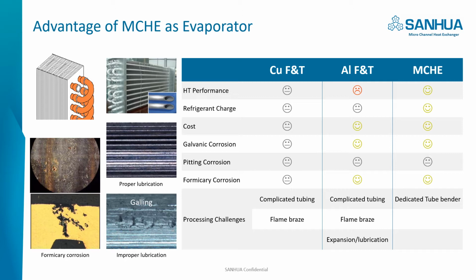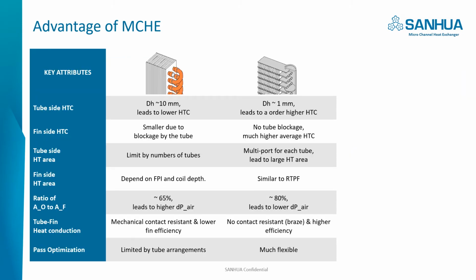Also, the industry uses lots of aluminum fin tube heat exchangers to reduce the cost, but still that's challenging at the processing manufacturing. For example, the expansion and the lubrication is more difficult to the aluminum fin tube heat exchanger. And microchannel heat exchanger has very good advantages compared to the aluminum, more on the heat transfer performance and also on the manufacturing reliability. From the heat transfer perspective, microchannel has advantages to fin tube heat exchanger.